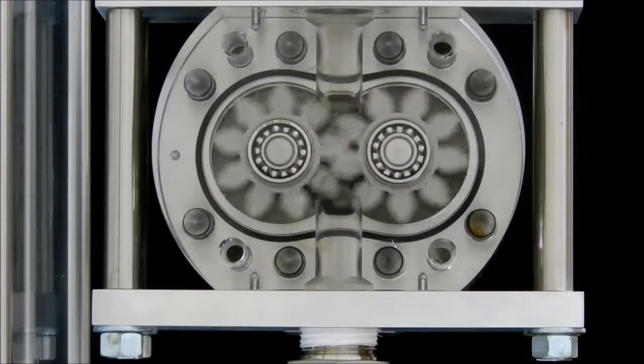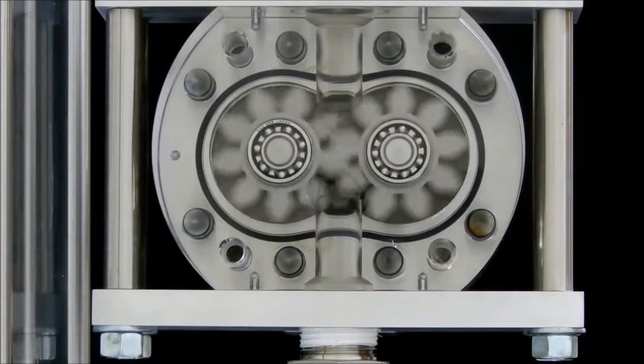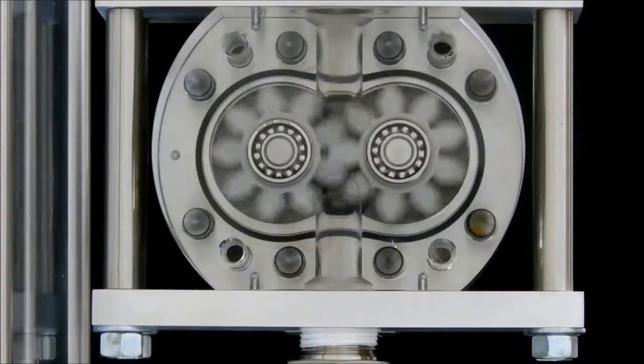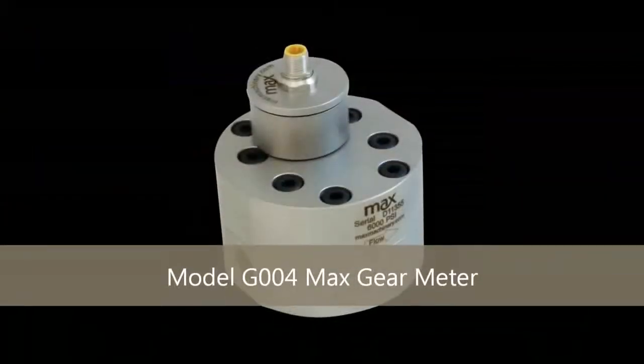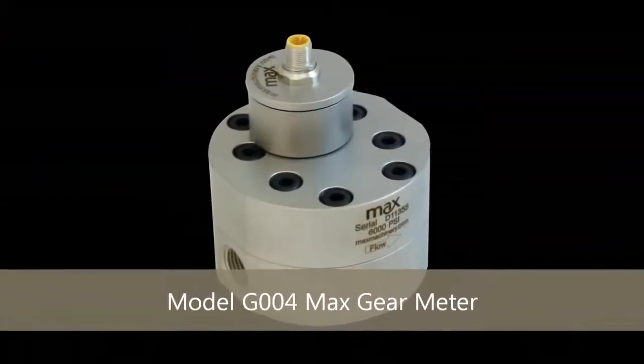One benefit to Max meters is the high-resolution transmitter that uses a magnetic signal to report the movement of an internal shaft as opposed to counting the gear teeth. In the frequency version of our model G004, for example, this means as many as 500 pulses per cc.